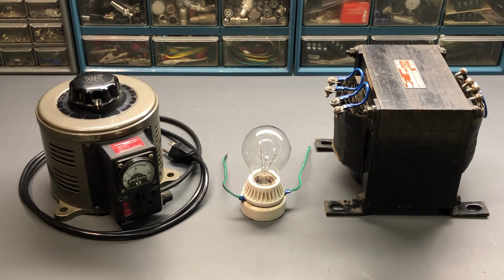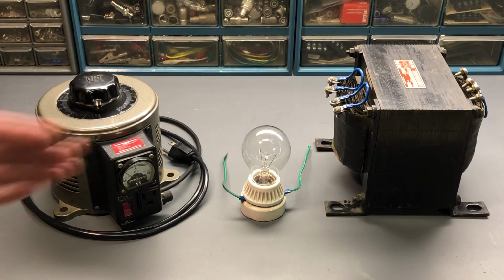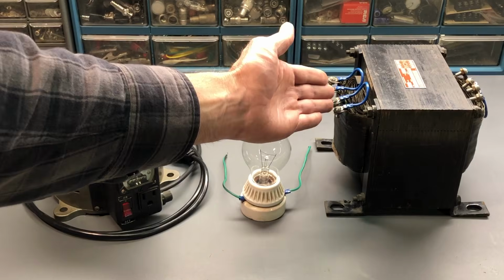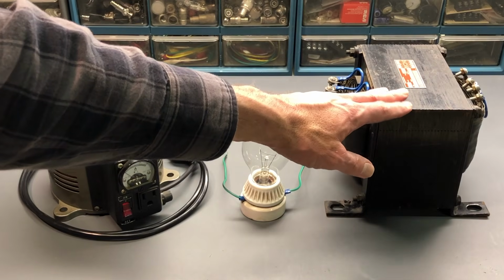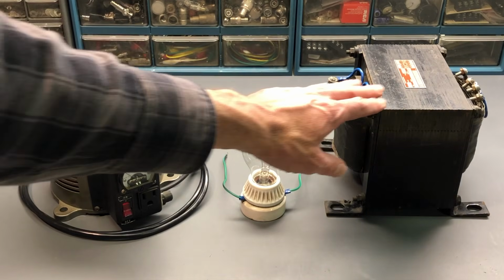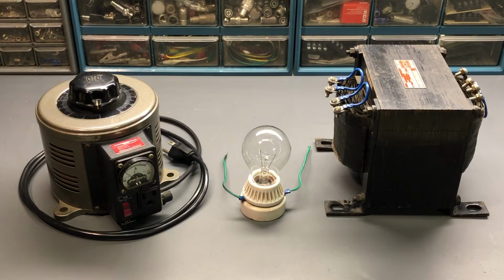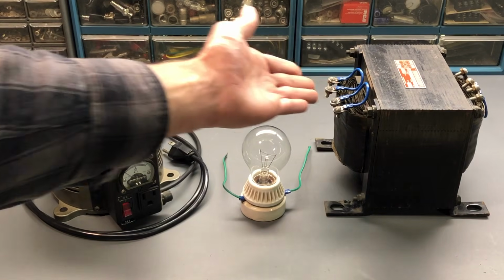Now, an isolated dim bulb tester typically would be mounted in a rather permanent fashion. Typically, you're not going to have these components across the workbench. You're going to want to have these permanently mounted. And again, I'll show my setup. It is a permanent installation. Certainly, a transformer like this that has exposed terminals needs to be in a protective housing, an insulated type housing, because you can't have terminals like this that are exposed.